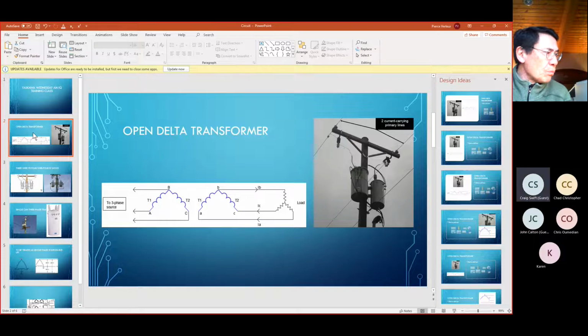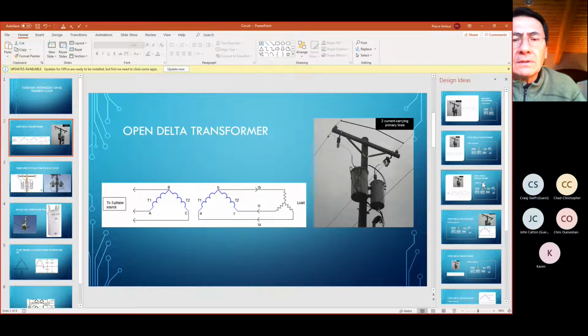Wow. And heavily concentrated in between Salinas and Napa. That's where the majority of the phone calls that I get on open delta systems come from. And we got one guy up there, he installs usually 60 to 100 drives a year, micros, which is where we prevalently run into the problem. He'll install 60 to 100 of them, and we'll usually get 3 or 4 of them out of the group that have a single phase and fallback issue.